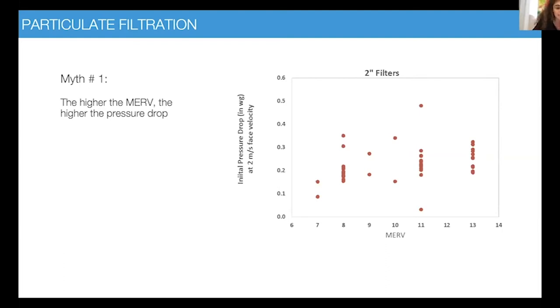Myth number one is that between MERV 13 and MERV 8, it's not necessarily true that a MERV 13 will increase the pressure drop on your system. This is extremely important. You can actually have a MERV 13 that has lower pressure drop than your current system. And I did this in my home and I do it for our clients. I ask them, okay, what do you have today? Let's look at the actual make and model of your filter. Let's get the data, which is readily available. Let's plot it, and then we choose a MERV 13 that is equivalent to what they have today in terms of pressure drop.